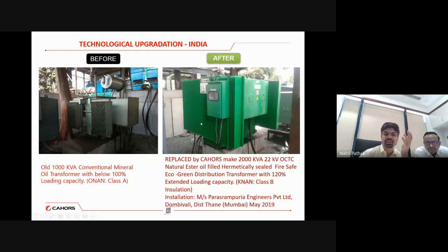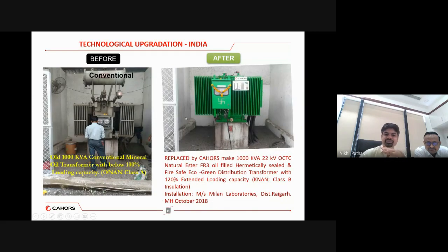So you can also see a few examples of the technological upgradation in India that we are already doing. The old transformers of a conventional design with the havoc of oil leakage issues and limitations to sizing and many other things. In place of a 1000 kVA transformer on the same foundation, we have installed a 2000 kVA transformer in 2019, and for these customers, we have the performance report also with us. Secondly, again, one more 1000 kVA conventional transformer, we straight away changed to a natural ester based hermetically sealed transformer, and this transformer is already running at 110% of the rated capacity. Even I can share with you the contact details of the customers and all. So it is already there in Mumbai, and it is going on fantastically.